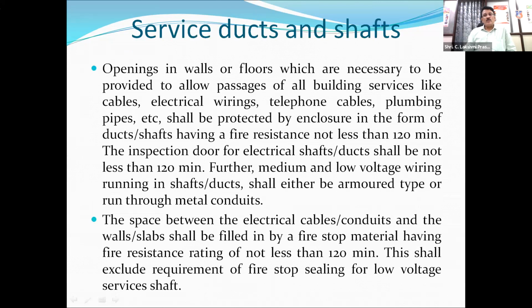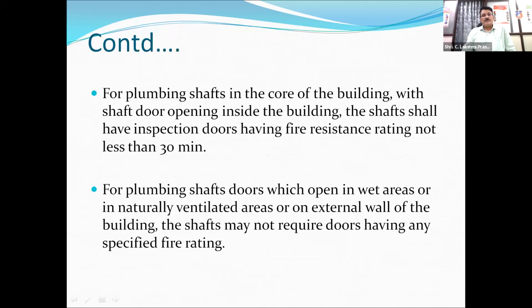Then the shafts, like the plumbing shaft or electrical shaft, should have doors with 2-hour fire resistance. The space between electrical cable conduits and walls or slabs shall be filled with fire stop material having a fire resistance rating of not less than 120 minutes. This 120 minutes is the minimum prescribed for various fire stops. Plumbing shafts should have doors with not less than 30 minutes fire rating. In most buildings these are kept open without any protection or door, so they are very dangerous. Plumbing shaft doors which open in wet areas or naturally ventilated areas or on an external wall of the building may not require doors having any specified fire rating. When you are meeting this condition, then the fire resistance rating of the doors is not required.